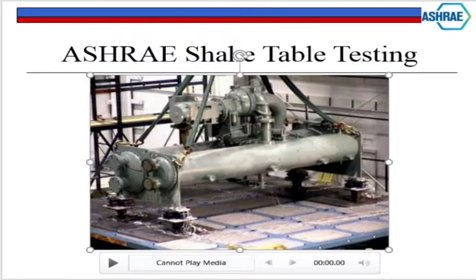So what we did, as ASHRAE, was test a lot of this equipment, trying to find out what the best seismic restraint was that you could use. Most seismic restraints are basically some steel framework and some rubber. Well, how thick should the rubber be? How hard should the rubber be? And what kind of air gap? In a seismic restraint you have to have some kind of air gap for the vibration isolation to work in day-to-day, everyday use, and then it locks itself out when the earthquake comes.